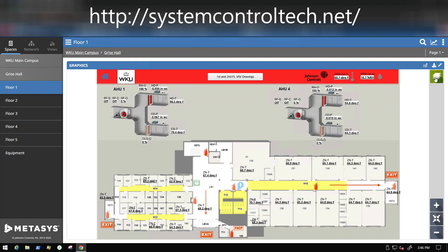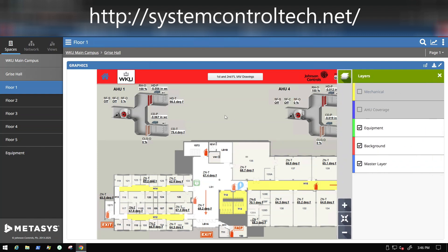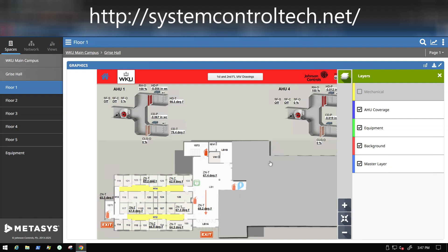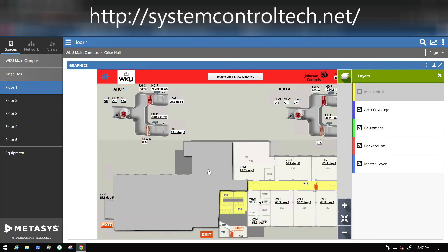So the feature that we're going to look at is the layers, and that is going to be found here. This basically looks like a stack of books in the upper right-hand corner of your display. I'm going to press that and you're going to see that I have a couple of different unchecked layers here — this is the air handler coverage layer and this is a mechanical layer that we'll talk about in a few moments. I'm going to check the air handler coverage layer, which will turn that layer on. Instead of hovering and highlighting just an individual room, it allows me to show the coverage area of the air handler. When I hover over it, it tells me what I'm going to navigate to and which air handler it is.